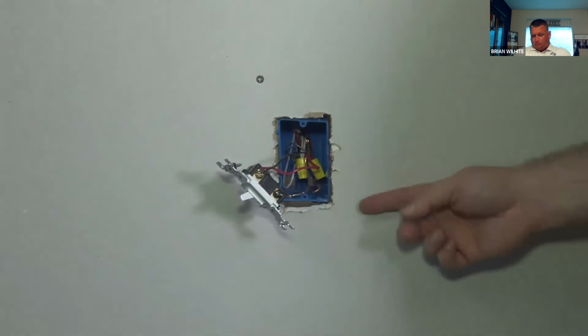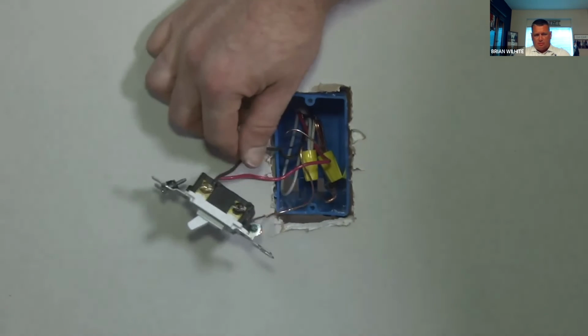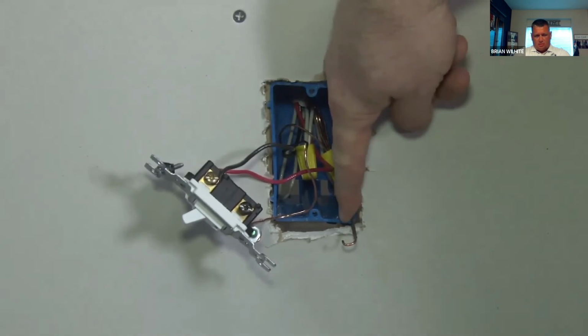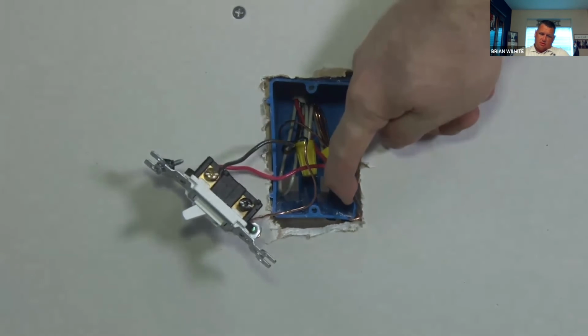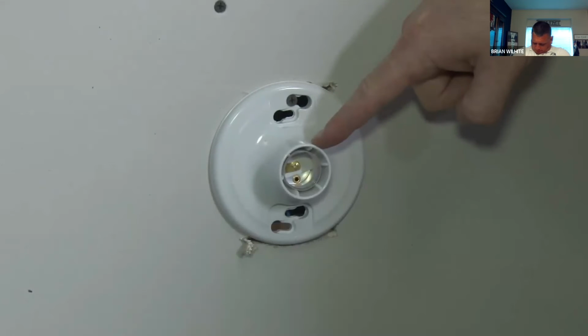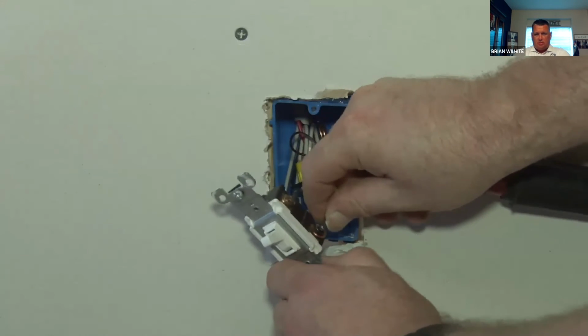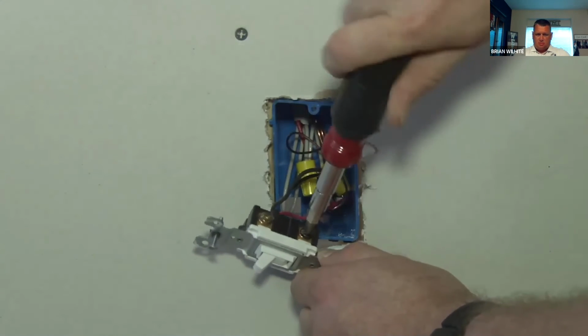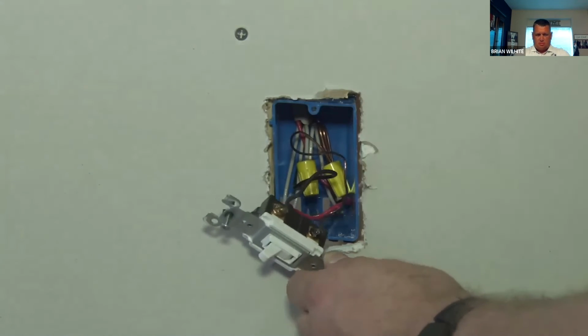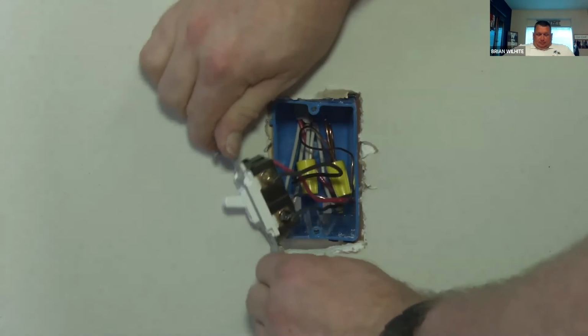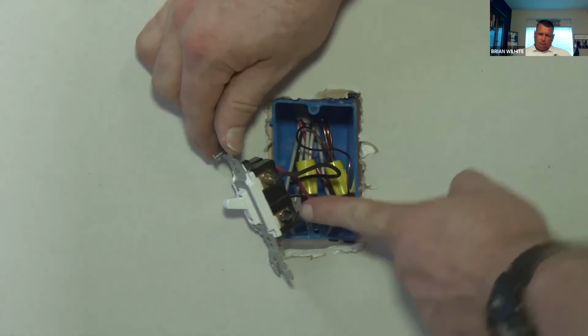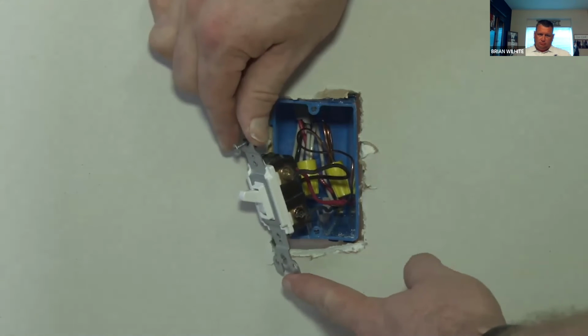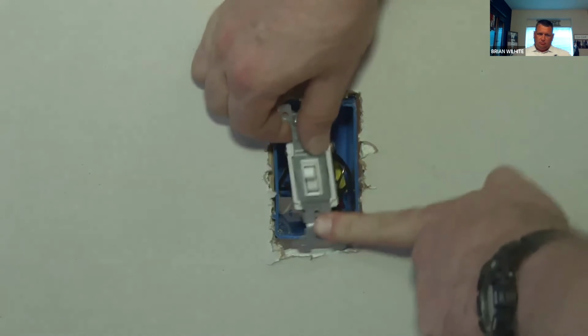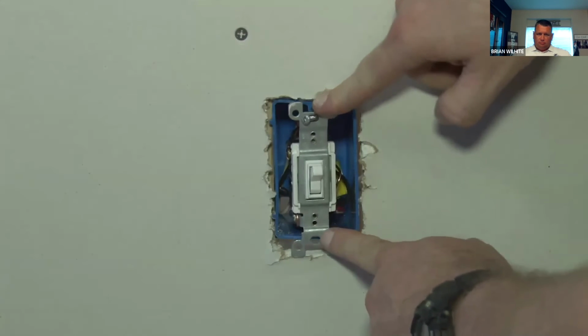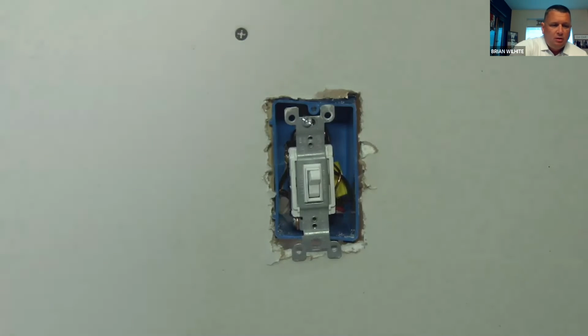In our second box, we only have one wire left, to where this wire will end up being, in this case, a black wire, and that black wire is the wire that carries power to our light fixture. That final black wire is what will connect to the common terminal on our three-way switch. Notice that when making connection to threaded terminals, the wire goes around the threaded terminal in the direction of tightening. Once we're finished making those connections, we can turn the power back on and check it.